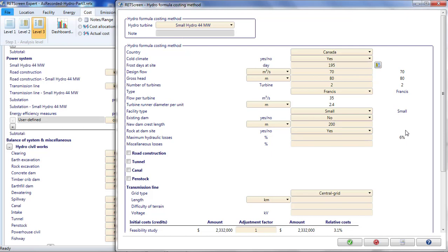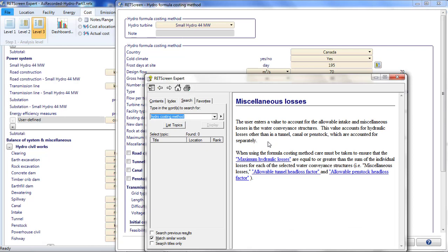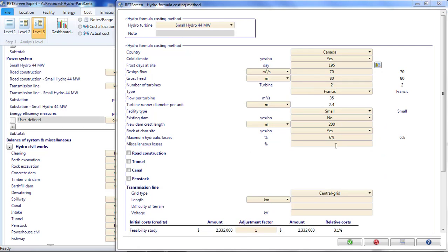For the maximum hydraulic losses, I carry over 6% from the energy page. I'm tempted to carry over 2% for the miscellaneous losses, but that would be a mistake. If I look in help, I'll see that the miscellaneous losses in the energy page refer to parasitic electrical consumption, transformer losses, and the like. In the formula costing page, the miscellaneous losses are hydraulic losses, not occurring in the tunnel, canal, or penstock. I'll enter 1% here.